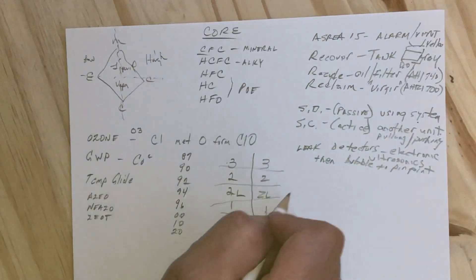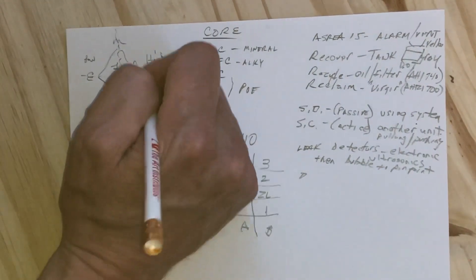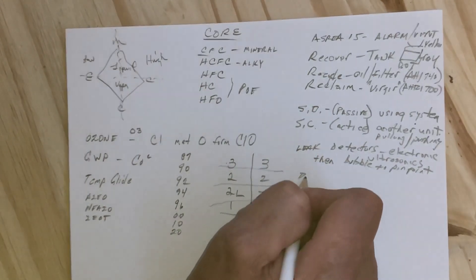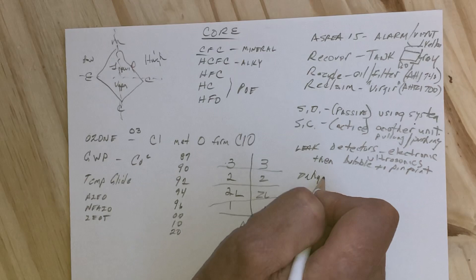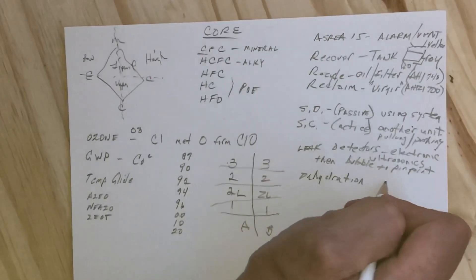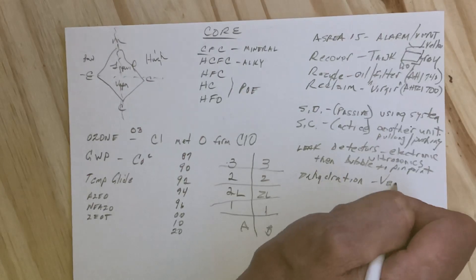After we recover, recycle, reclaim, some sort of major repair on the system would be considered any one of these. They have heat exchanger in some test questions I've heard, but dehydration is where we're going to get our vacuum down to 500 microns and hold.